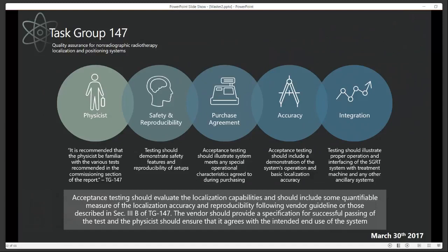The accuracy, this is where some of the overlap with commissioning comes in. There should be a basic localization accuracy test. It doesn't have to be to the level of precision, but you should be able to demonstrate the accuracy of the implementation of SGRT before the vendor leaves. You also need to be able to demonstrate that the integration with your LINAC, with your ROIS or your treatment planning system is also adequate and functioning correctly. There's a number of tests in Section 3B of TG147. That's the box down at the bottom there.